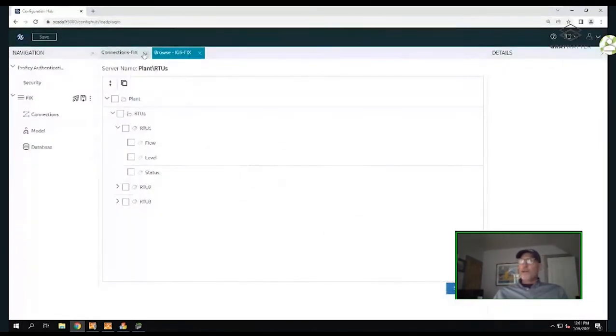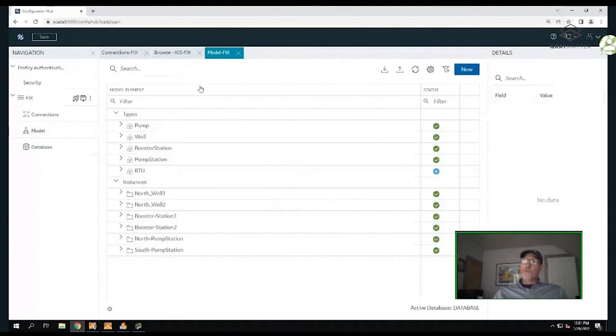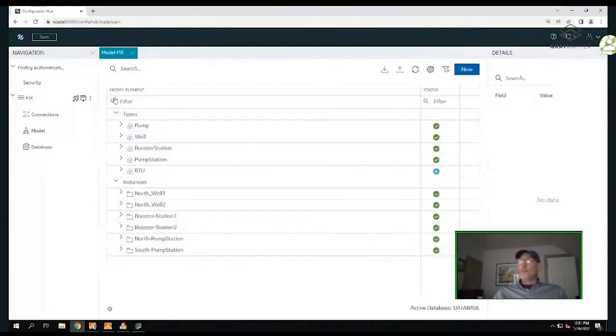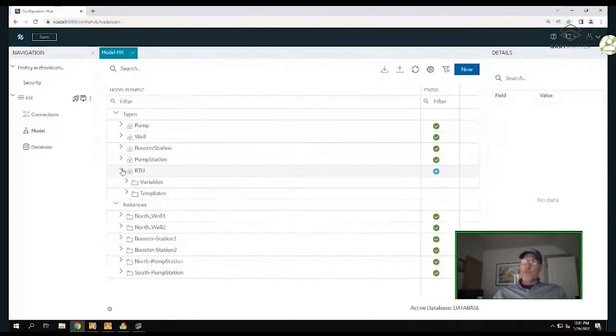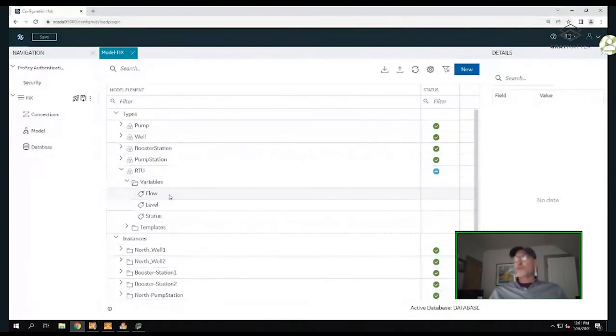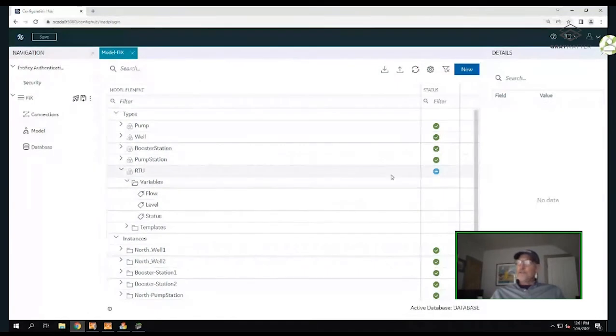I did my browse and connection. Next, I'm going to look at the model and see what it built. It builds another tab, and in this window it built an object type called RTU. In that object type I have variables - typically tag names linked to a controller. Once I have that, I can create instances of that type. But before I do that, I'm going to customize this particular type because I want to use the same type for multiple RTUs.